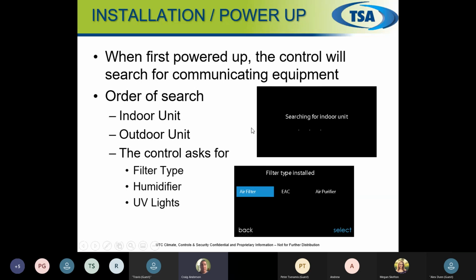If you have a communicating indoor and you have a non-communicating outdoor, at this stage of the process, once it finds your indoor unit, it's going to search for your outdoor. If it does not find a communicating outdoor unit, it's going to ask you a question. Do you have an AC hooked up to it? Do you have a heat pump hooked up to it? So this is where we go through the next steps if we don't have an outdoor communicating unit, which we'll touch base with in some more slides as well.